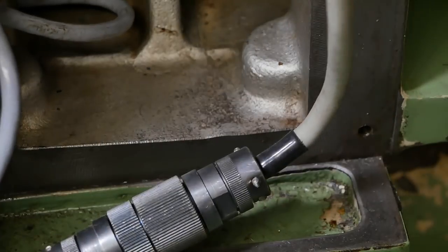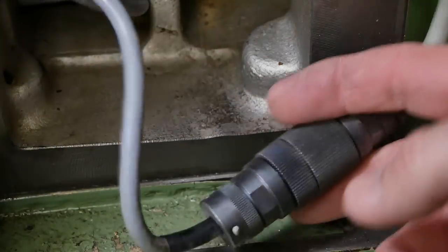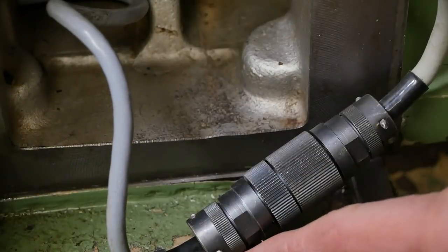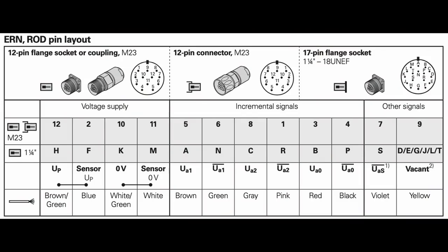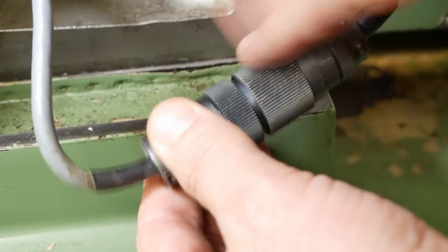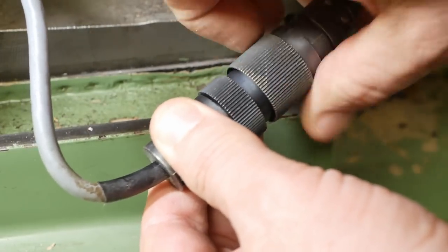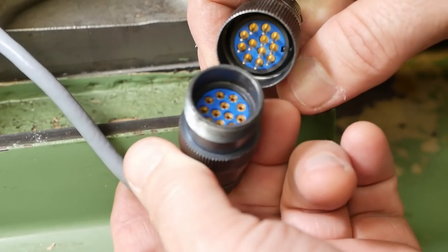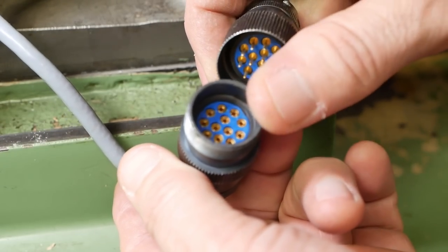Okay well that's not going to help me because the Heidenhain wiring terminates here and it's Schaublin wiring from there on in and they could have used any coloring. Heidenhain wiring is generally standardized. This is the pinout for a ROD 620. It doesn't look like Schaublin's continued on with the same colors that's for sure. But wait a minute. If this is a standard Heidenhain 12 pin plug, those pin positions will be standard and I can work out the function from the pin position.